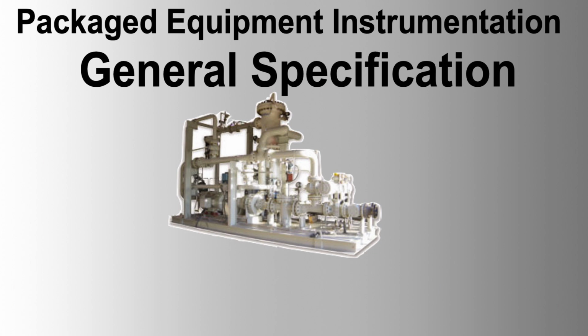Pressure gauges: Bourdon tube type for general local pressure measurement. Gauge cases should be aluminum alloy, weatherproof, and black painted with 4.5-inch diameter dials. Gauges should have over-range protection to 25% above maximum pressure and be liquid-filled for vibrating installations. Instrument process connection should be half-inch NPT.